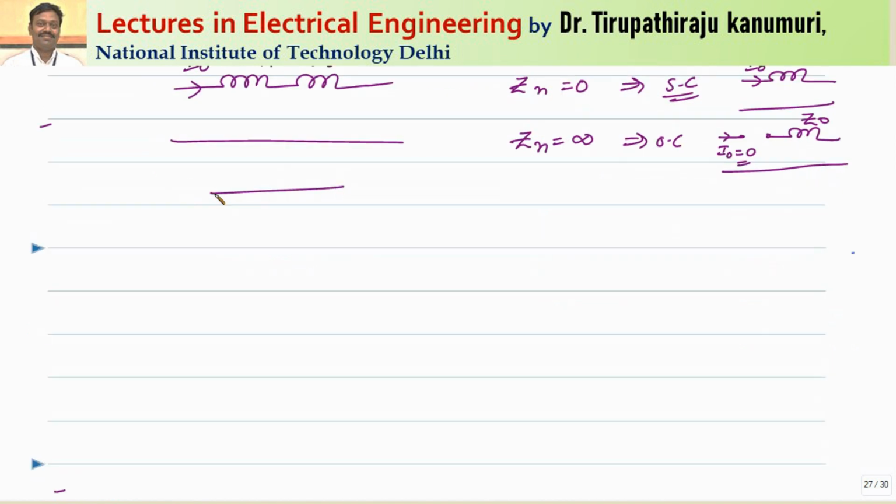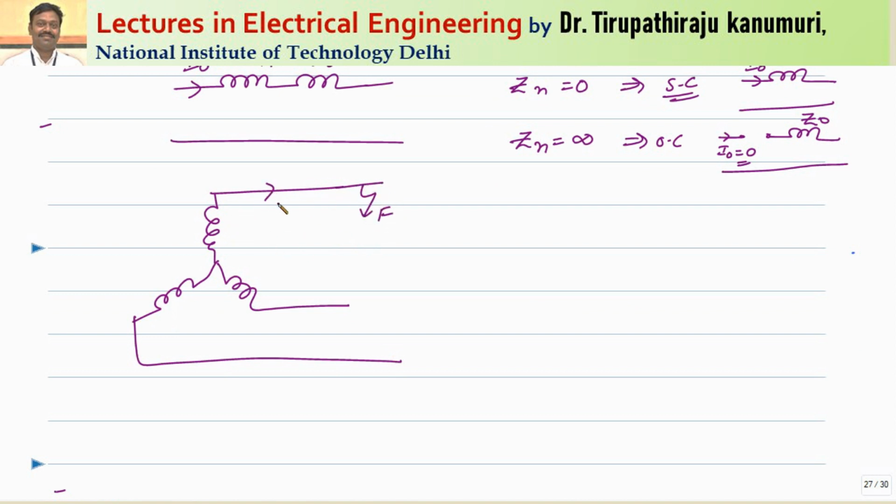What case am I taking? I am taking the case of a transformer, any one side. This is my transformer where my neutral point is not grounded. Whenever the fault happens here, this is my current IA, this is my current IB and this is my current IC. As the neutral point is not grounded, because it is not connected to ground, automatically at this neutral point the sum of the currents IA plus IB plus IC should be equal to 0.